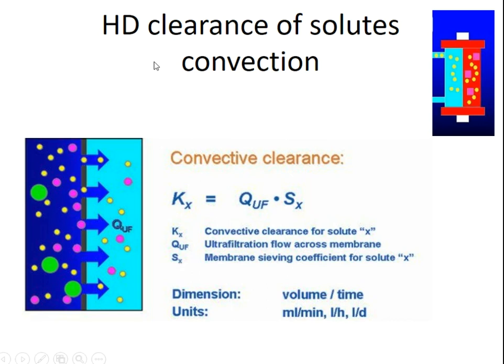When measuring hemodialysis clearance by convection, since convection depends on the ultrafiltration rate, we incorporate Quf (ultrafiltration flow rate). Convective clearance depends on both the ultrafiltration flow rate across the membrane and the membrane sieving coefficient for a given solute.